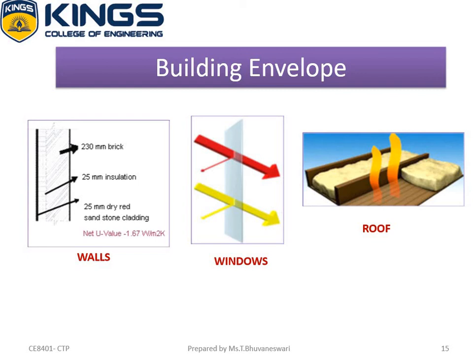The next thing is roof. 35 mm thickness insulation with reflective glazed tile paving. The glazed tile reflects heat off the surface because of the high solar reflectivity and infrared emittance, which prevents heat gain and thus helps in reducing the cooling load from the building envelope.